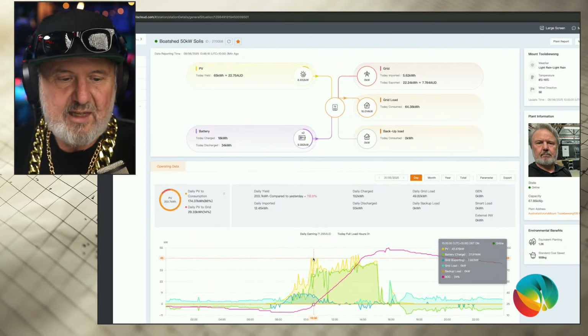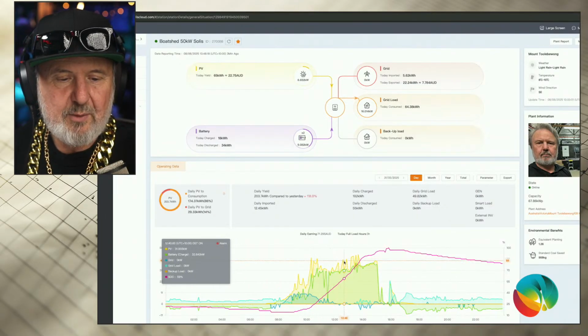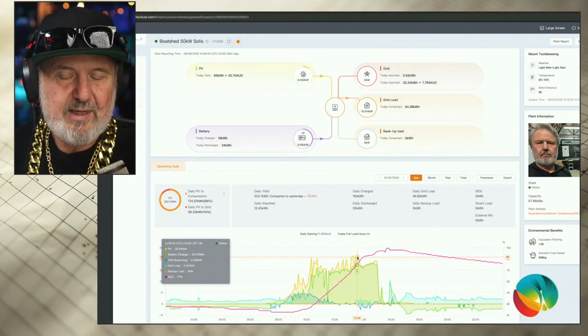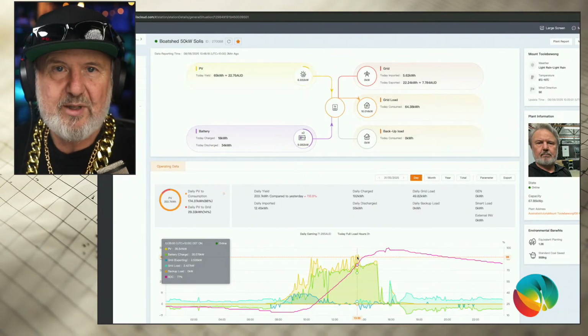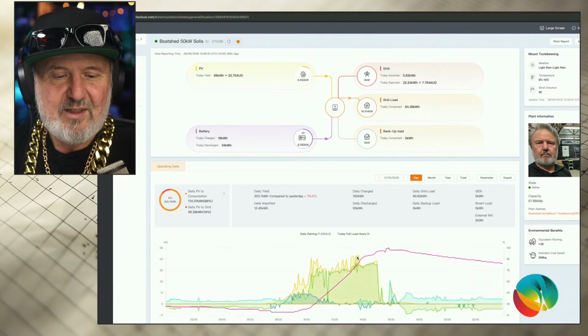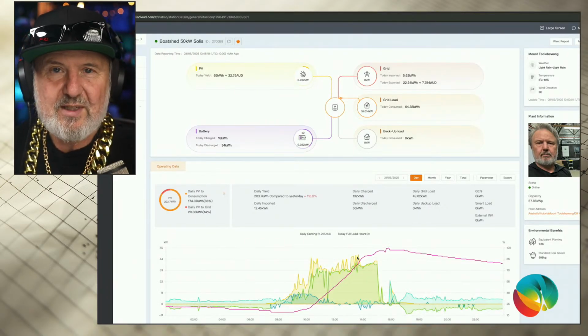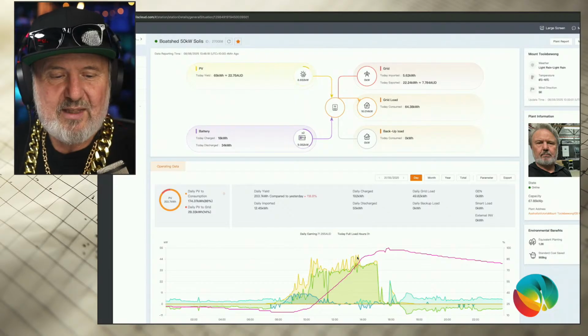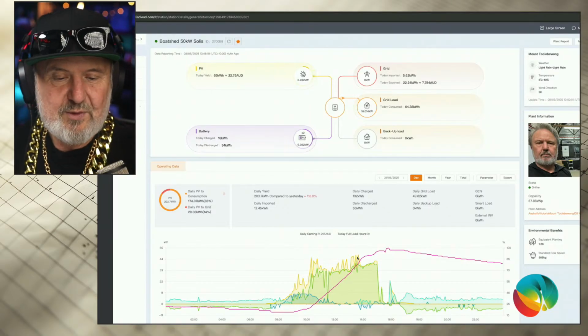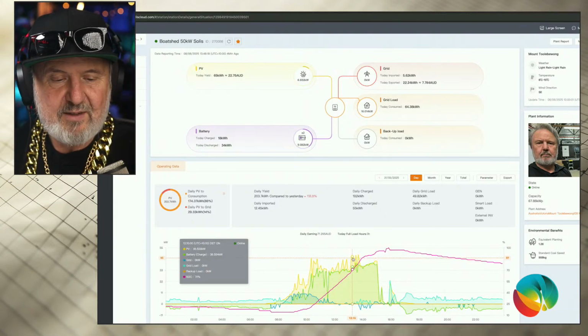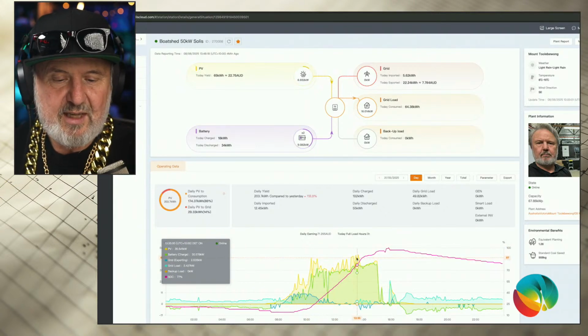If you look at the yellow line, which is the PV, the reason it's spiky is we were still tweaking the frequency settings a bit. Occasionally it would pump too much power back to the microgrid, the grid-forming system, and cause the frequency to spike, and it would stop generating for a few minutes before coming back online. Once we've sorted that, this should be a very flat generation profile on a sunny day.